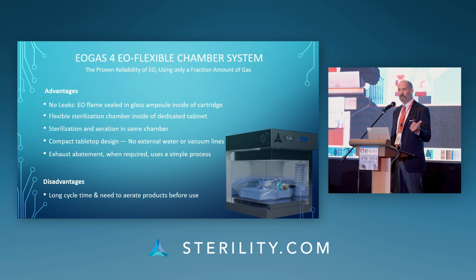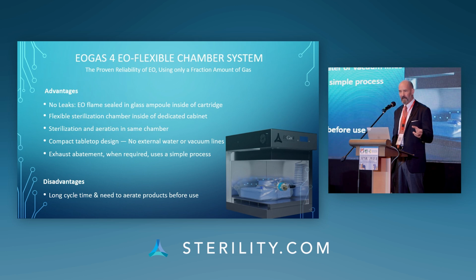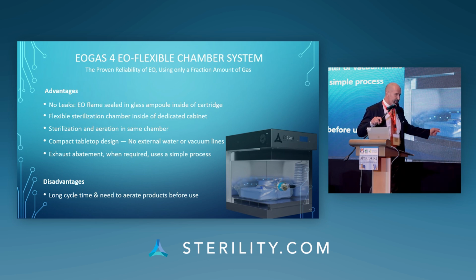We're using very small cartridges, and these cartridges contain ethylene oxide that is flame sealed in glass. And a glass ampule full of ethylene oxide is not going to leak. The glass ampules are protected in a plastic cartridge. This is the only way that we have found to make sure that you have a system that does not leak gas during storage.